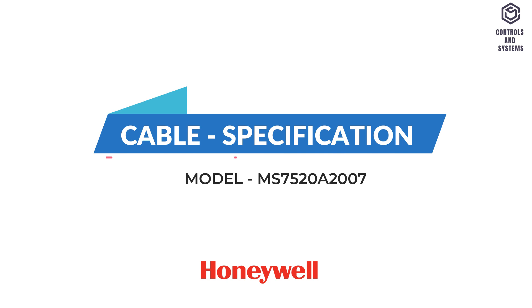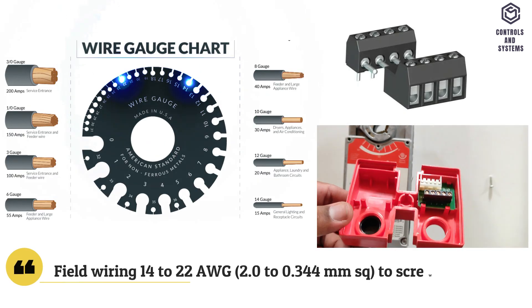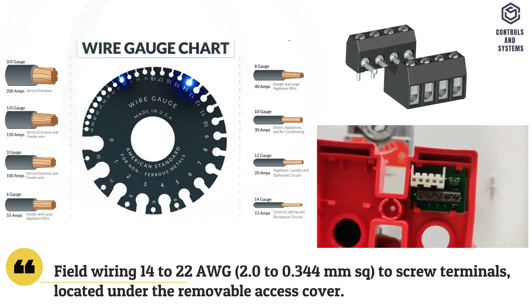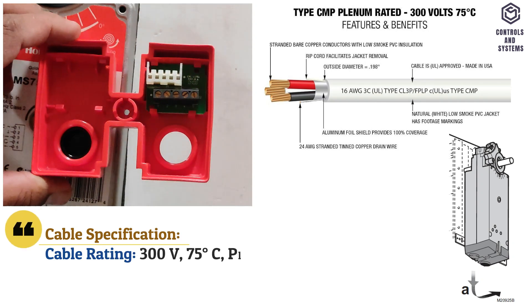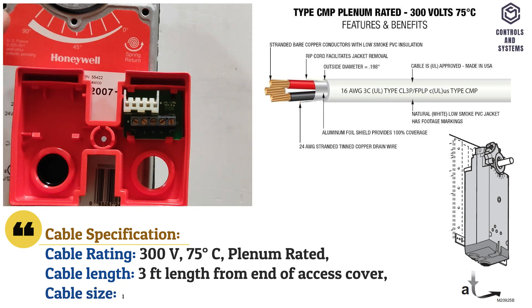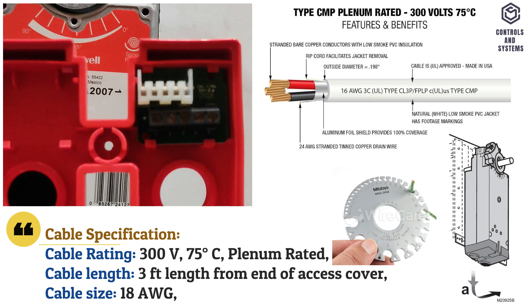Cable specification: field wiring size is 14 to 22 AWG to screw terminals located under the removable access cover. Cable rating is 300 volt at 75 degree celsius, plenum rated. Cable length is 3 feet from end of access cover, cable size is 18 AWG.